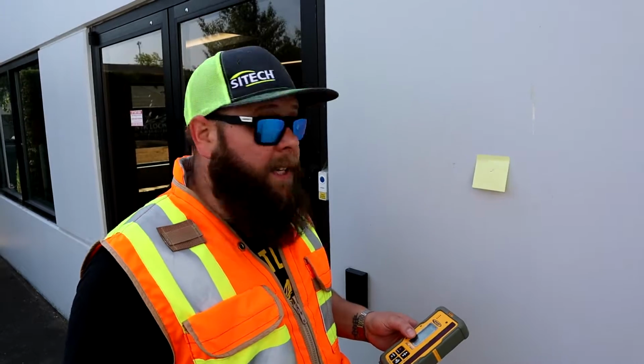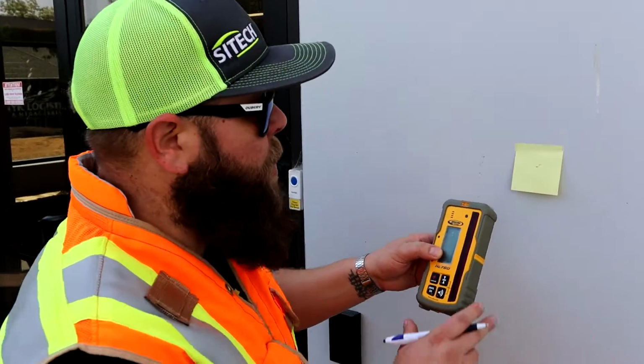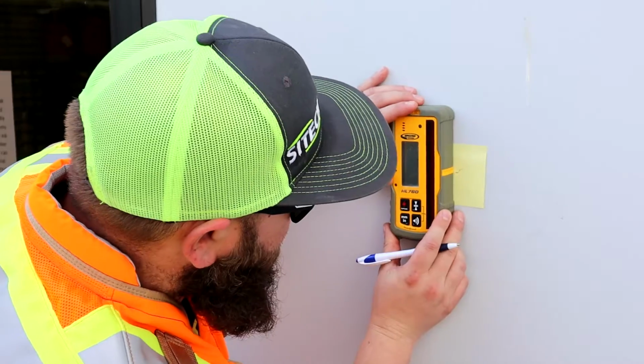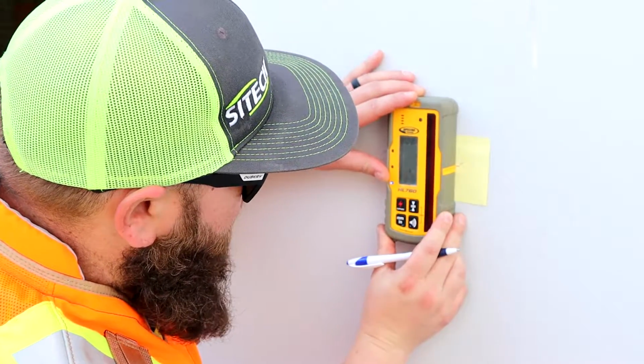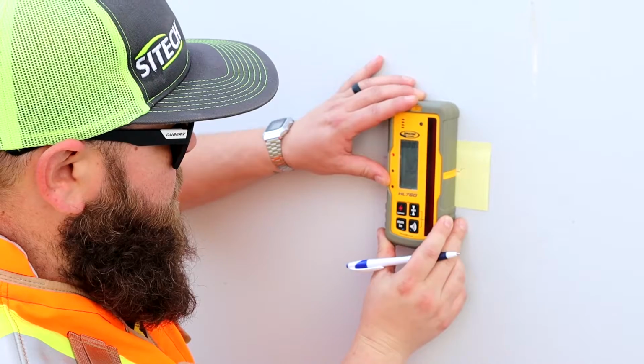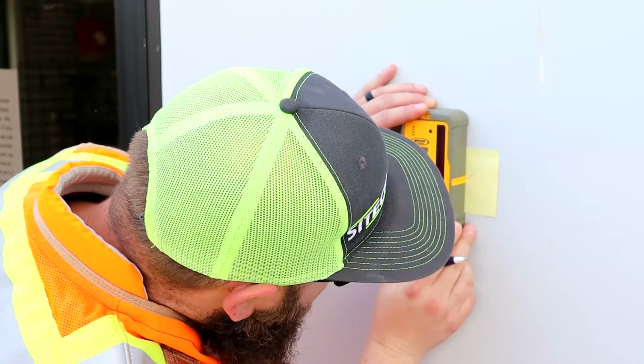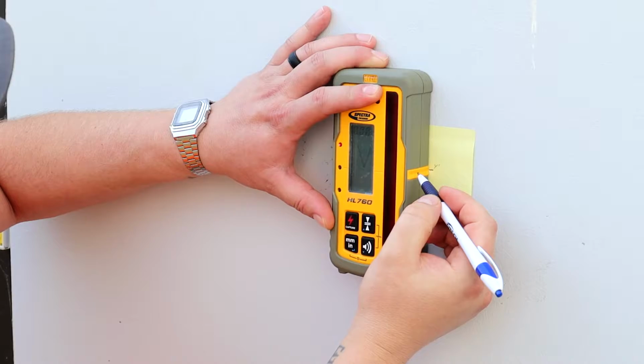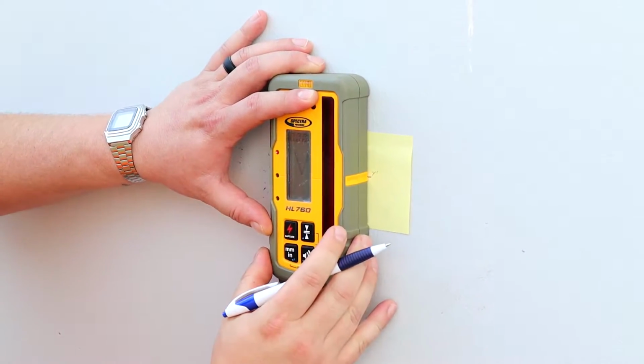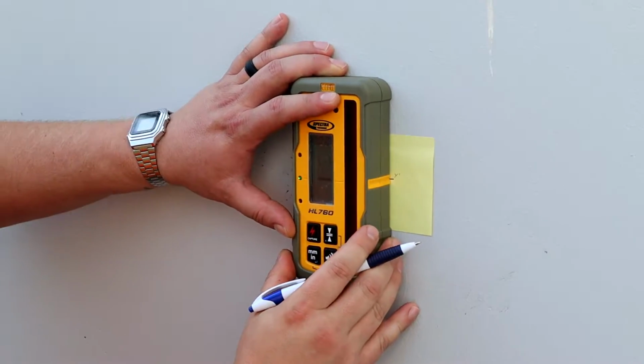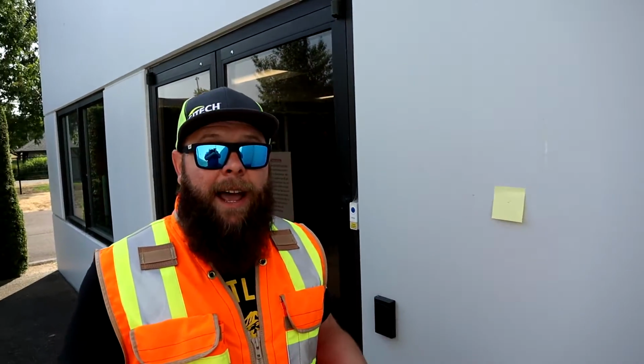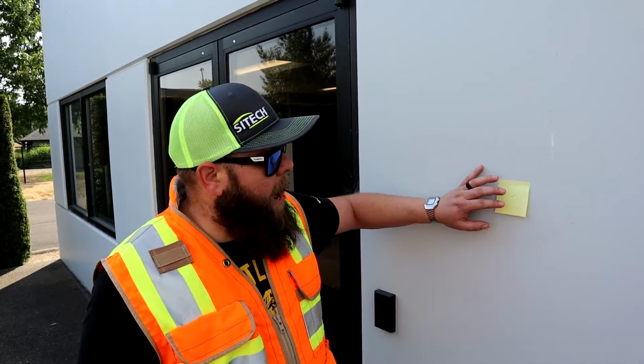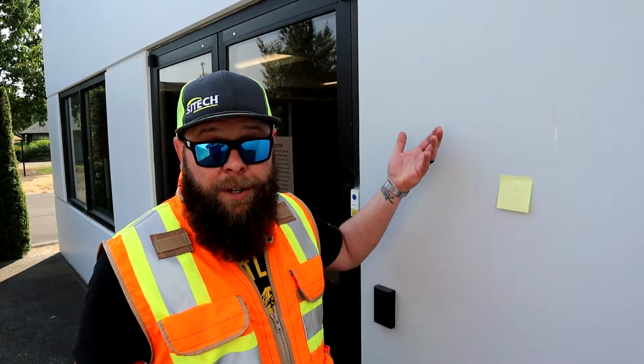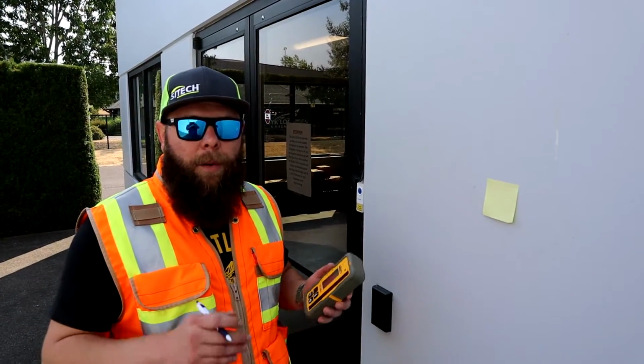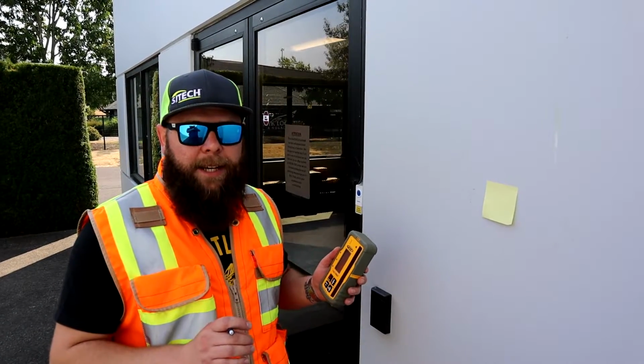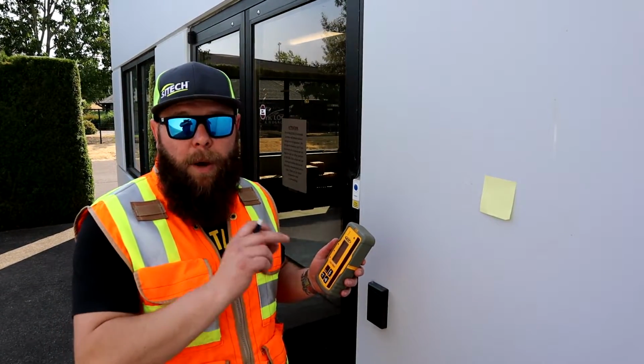So now we've rotated the laser, and I'm going to show you Y2 and show you that the axis is in calibration. You can see that my mark and my tone is in the same place here. So that axis is calibrated. Now we're going to show you the X-axis that we've taken out of calibration, so we can show you the actual two marks that will show out of calibration, if that makes sense. So now we are going to show you the X-axis and the error between both sides.